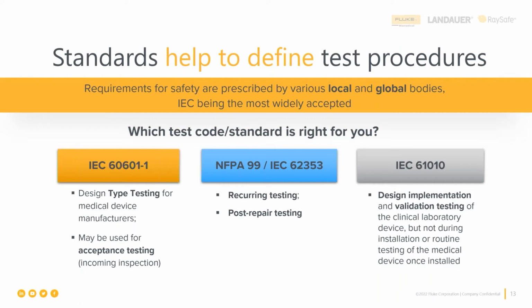The other standard that falls underneath that umbrella is the IEC 62353, and we'll talk a little bit more about that as we go through the presentation. Third one, IEC 61010, really is about clinical laboratory equipment. And once again, we'll talk more about that as we go through this presentation. It also falls underneath the IEC 60601 umbrella. All right, so just so we clarify, what are the standards that guide how we do the tests and what are the testing limits for each of the tests that we're going to do when we make measurements about electrical safety.